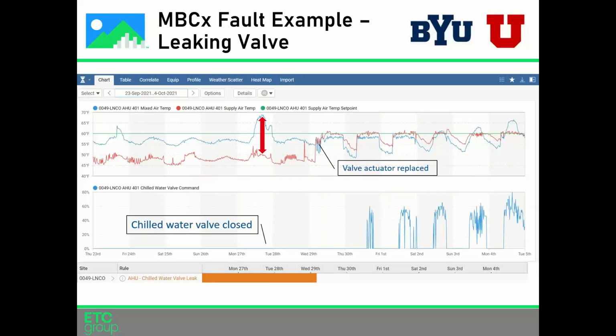Okay, I want to walk you through a couple of examples of faults and how they work. I kind of talked through this one a little bit, but I want to give you a more clear example of how this is working. Here we have an air handler with a set point of the supply air temperature, that's this green line, and a blue line representing the mixed air temperature coming into the unit. And then this red line represents the supply air temperature that's provided by that unit.